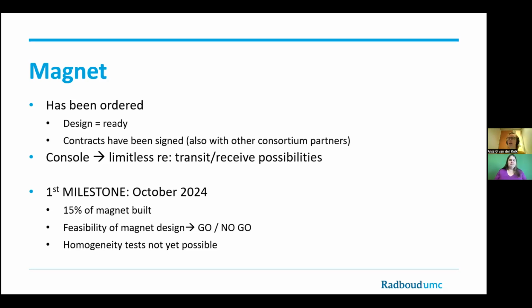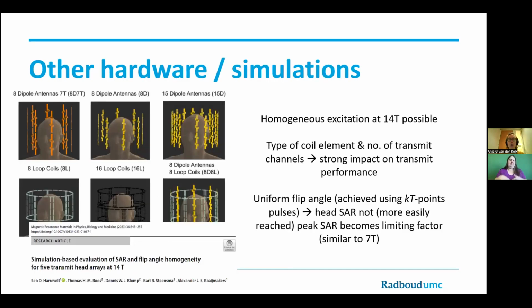Homogeneity tests for B0 and everything are not yet possible. You really need the entire scanner for that. However, we have not been idle. You can of course simulate a lot on 14T, and you can probably simulate a lot even on 20T. One example that has recently been published is about transmit head arrays at 14T. They found through simulations that homogeneous excitation at 14T is possible, but that you need to think about what kind of coil element and how many transmit channels you can use.